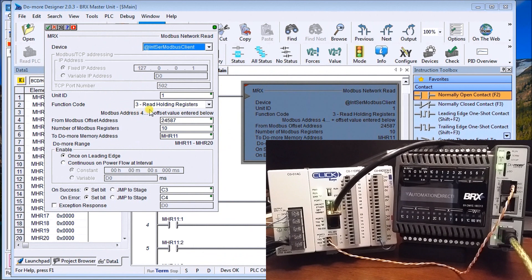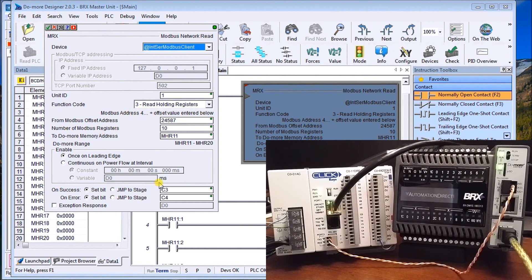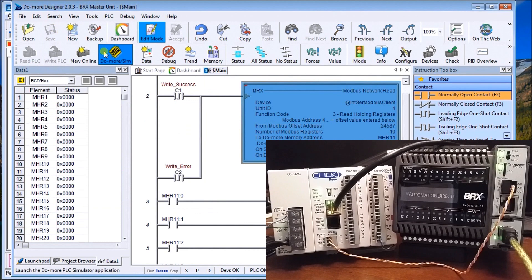Looking at the read instruction: we're reading holding registers, again with a Modbus address of 4 plus an offset — in this case 24587 — and the number of Modbus registers to read is 10. We're storing that in MHR11, and because there are 10, it goes from MHR11 to MHR20. There are also a couple of status bits — C3 and C4 — which set on if the read is successful or if there's a read error.